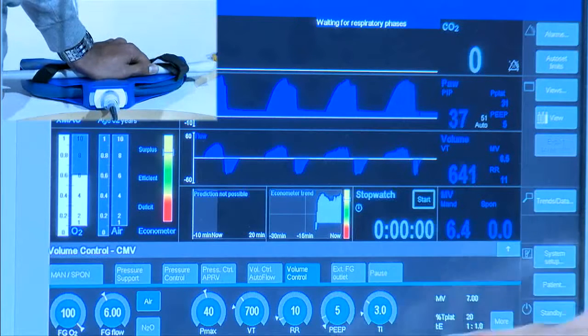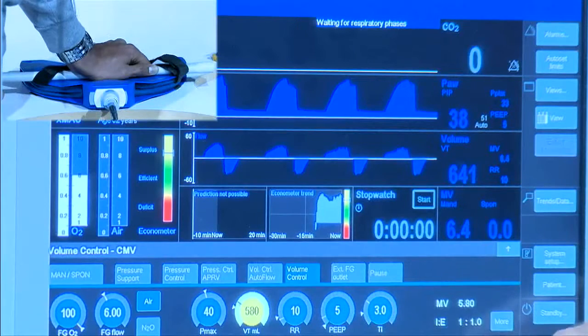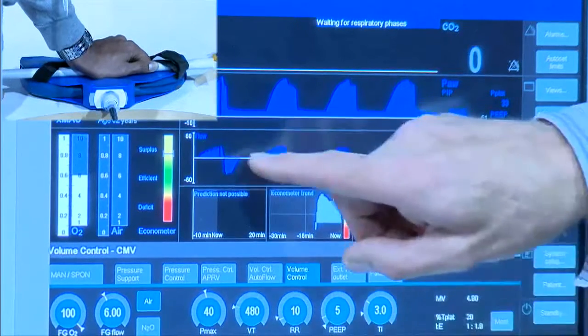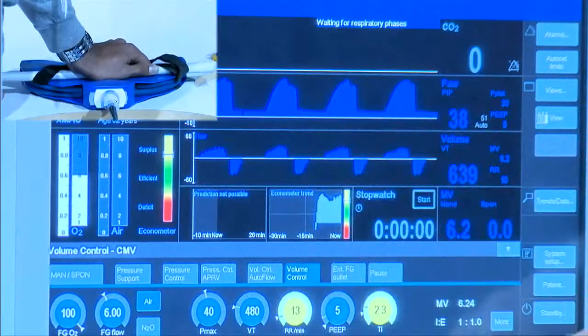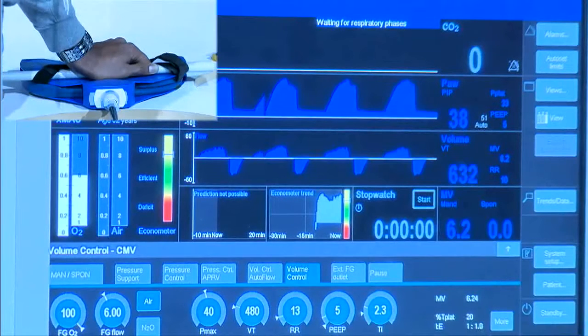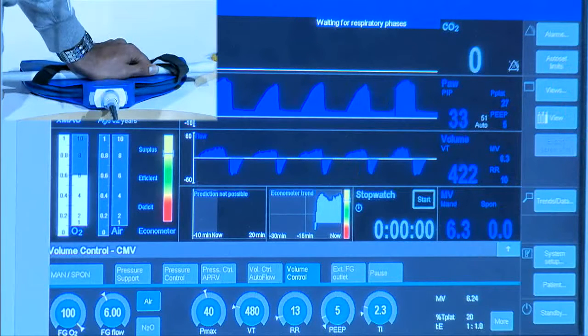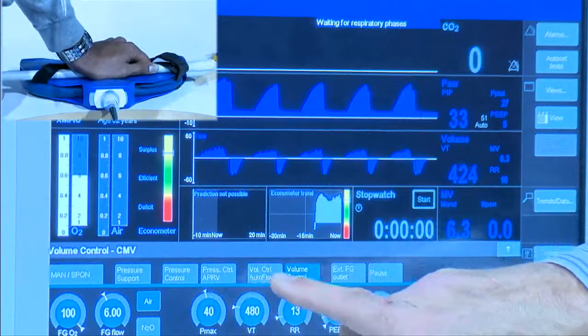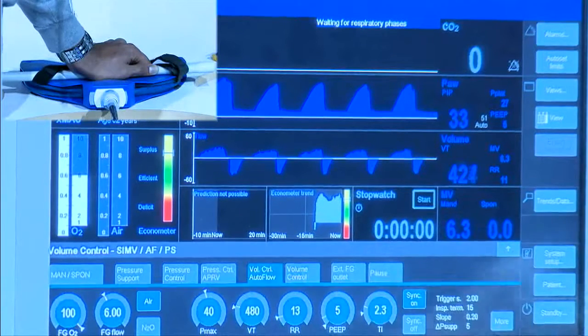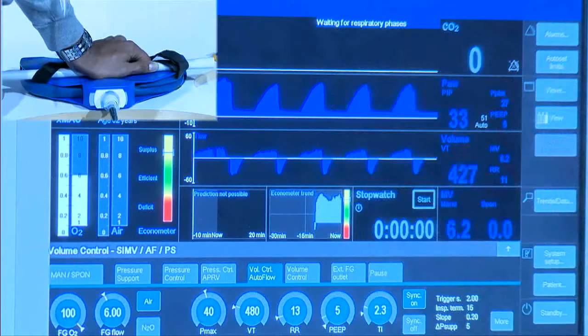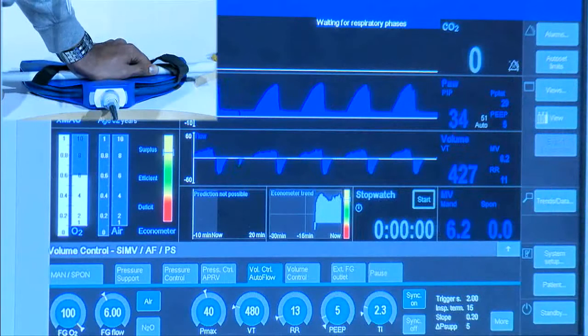So what I'm going to do is turn the tidal volume down and go faster, because we're wasting all that time in exhalation. Now in reality, you'll find often going to 1:1 will make a big difference. Okay. So that's dropped the pressures a bit because the tidal volumes are small. But what about we use volume autoflow mode, which is a volume guaranteed pressure control type mode. Let's just see how that goes.